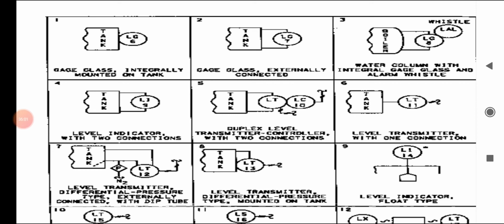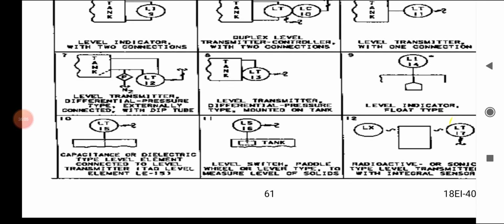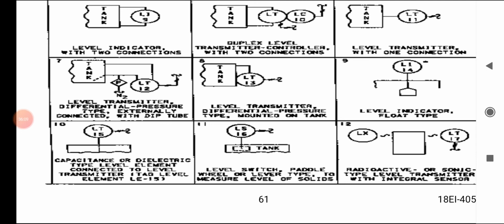Level indicator, float type as shown. Tenth one is capacitance or dielectric type level element connected to level transmitter, tag level element LE15. Level switch, LS: L for level, S for switch, paddle wheel with a lever type to measure level of solids. So 12 is the LX and LT, radioactive or sonic type level transmitter, with integral sensors.